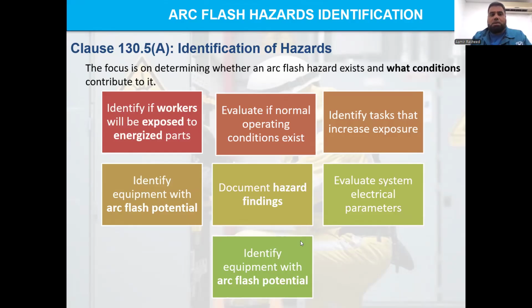If you are exposed to energized parts and you are working in an abnormal condition, does an arc flash exist? If the answer is yes, then there is a next step that you need to do. Keep it in your mind: if no hazard exists, no arc flash control is required. If a hazard exists, then we move to the next step, which is called the risk assessment.